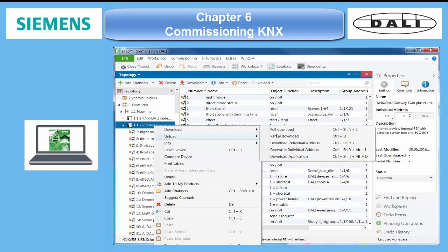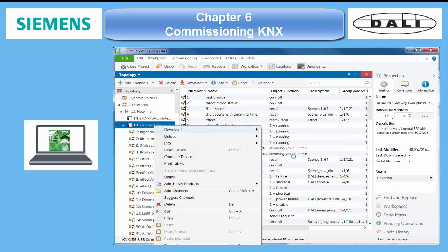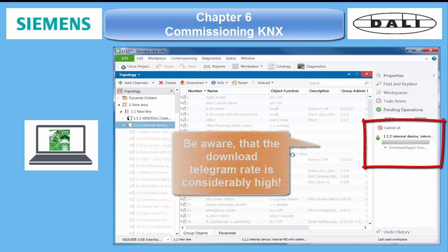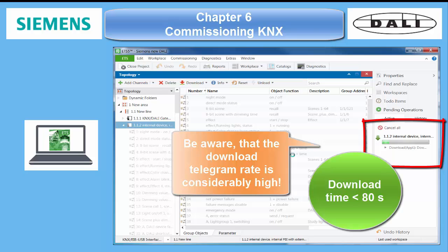Some remarks on the KNX download. The overall download time has been optimized dramatically in comparison to the N14102 or other earlier Siemens KNX DALI gateways. In the local line — that is, without line couplers or IP routers en route — it shouldn't be longer than 80 seconds at no extra busload using ETS5.